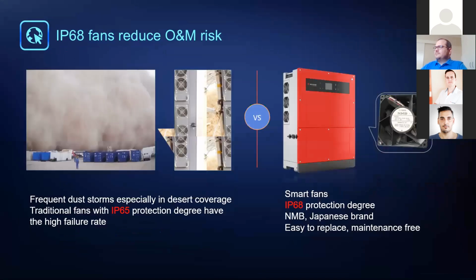Another big selling point for GoodWe commercial inverters is our smart fans. So fans are usually a point of failure within inverters, and GoodWe has incorporated these smart fans, meaning that the speed of the fan adjusts according to the temperature, both the ambient temperature and also the internal temperature of the inverter. The speed of the fan adjusts according to that temperature. And then we almost over design when it comes to the fans.